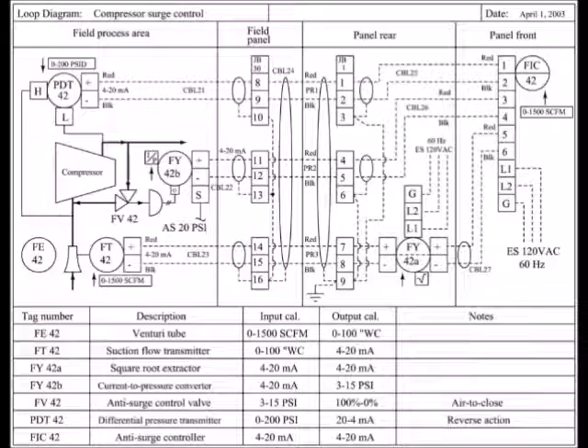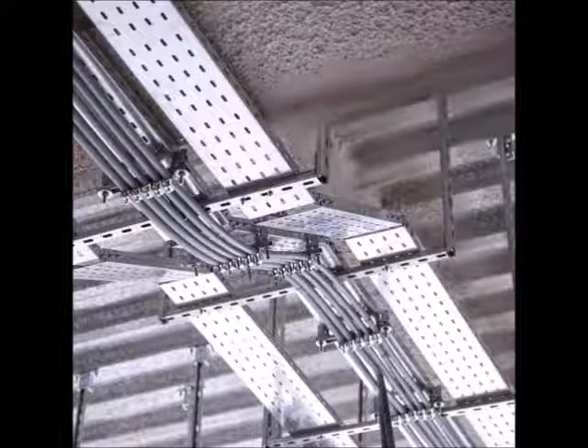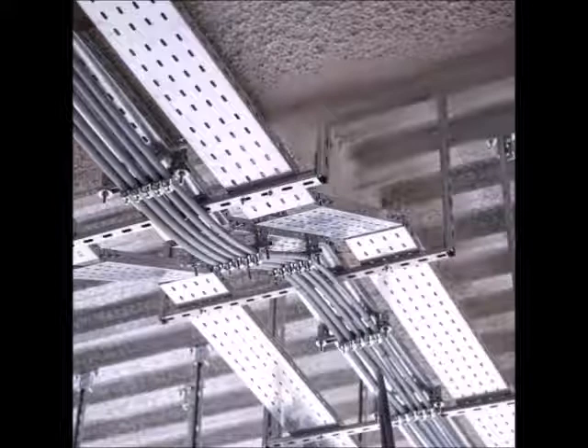Back to the loop diagram. The cabling from field to panel. Typically in greenfield plants, cables sheathed in armoured sleeves may be pulled through underground ducting or laid underground by cut and cover. This is to save overhead space. However, the cons of this is that cable repair is very difficult. Alternatively, cables are neatly tucked and run via cable trays. This method typically uses up more copper cables which increases the cost.